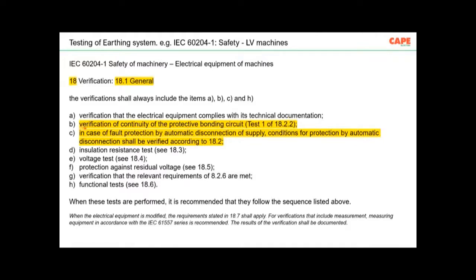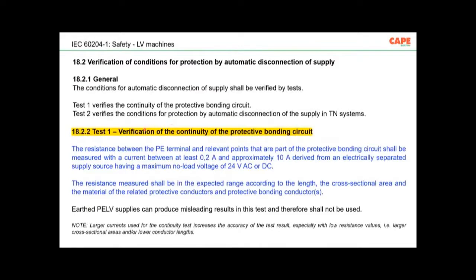The first testing you see here, verification of continuity of protective bonding circuit. So the equipment or the machine is earthed, in the sense the PE conductor, the PE terminal of that machine is connected to the equipotential bonding conductor. So the verification of continuity of that earthing conductor or that particular wire must be tested and ensured. That is earthing. Number two, in case of fault protection by automatic disconnection of supply, condition of protection by automatic disconnection of supply shall be verified. So the first one, clause 18.2.2, I show you what exactly these tests mean.